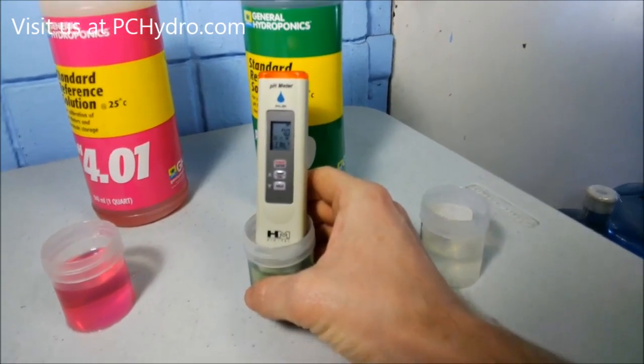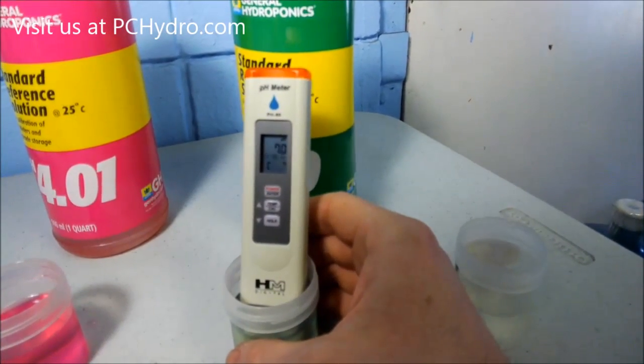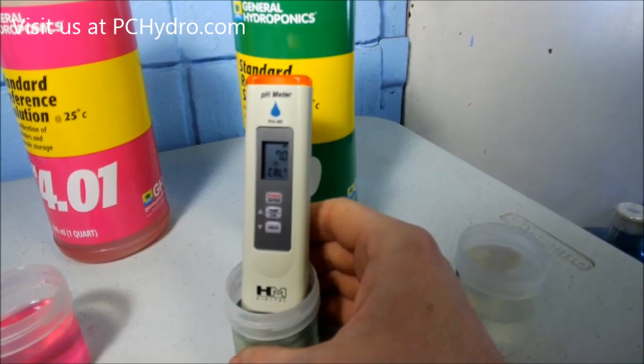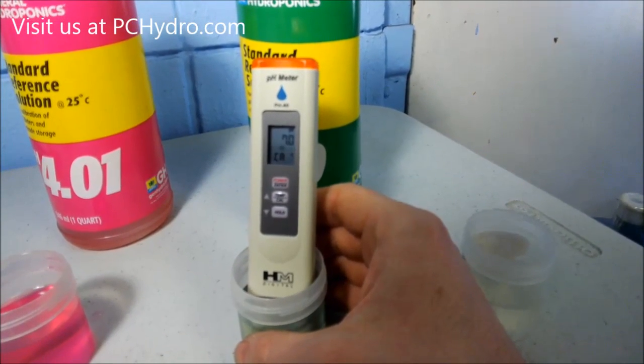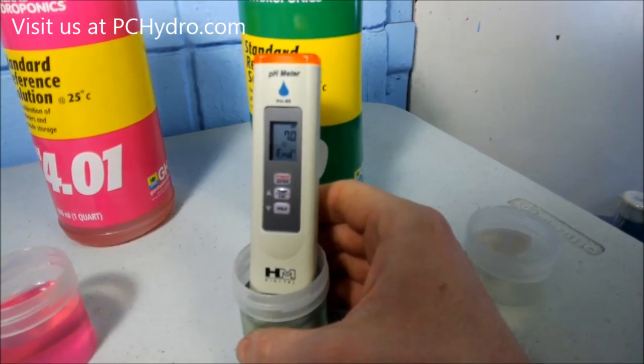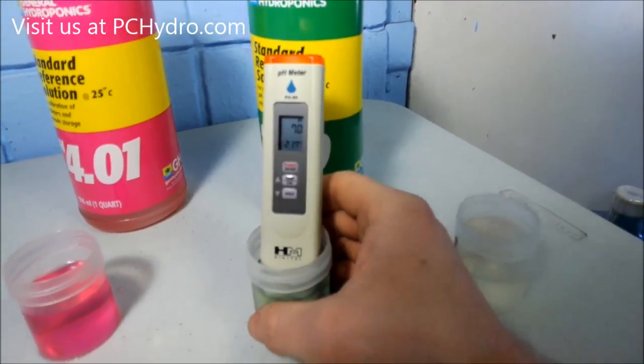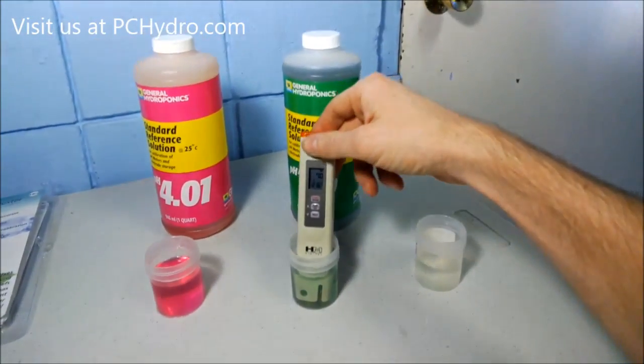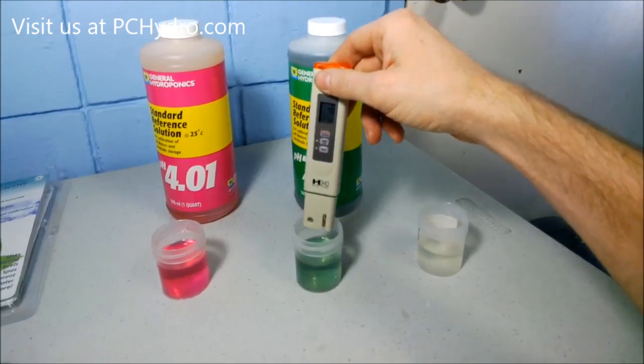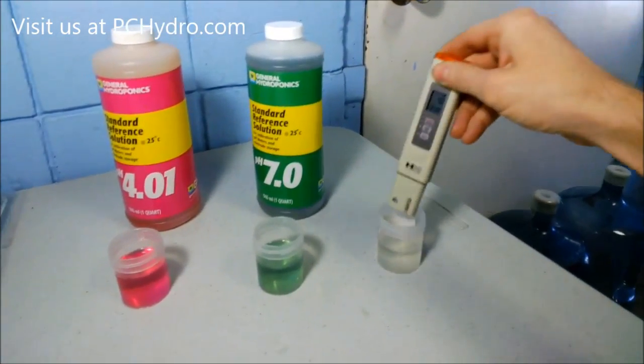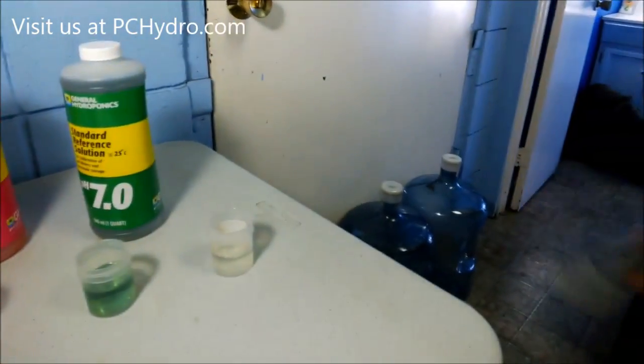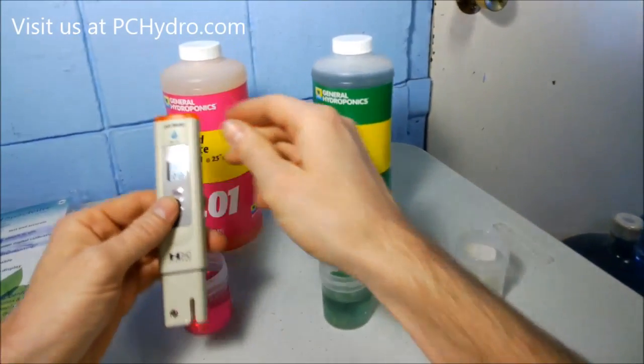And you can see it's flashing 7.0, and it's going to start scrolling the letters cal, and that means it's calibrating. And there it's done, basically. It says end, it's calibrated to 7. And that's the process for a 1-point calibration with pretty much any pen. You rinse it off, and then we're going to go ahead and do the 4.0.